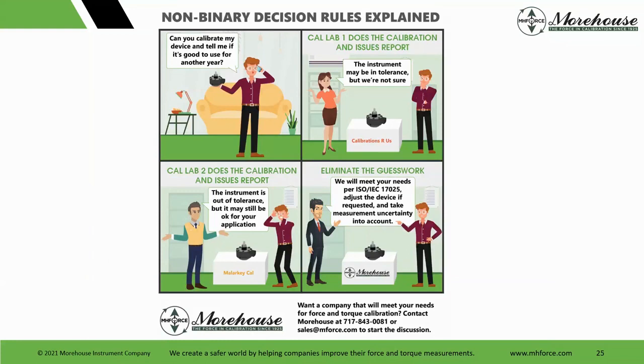So here's what we ran. We came up with this cartoon for it because it's really ridiculous, right? The instrument, so we do the calibration. This is a conditional accept. The instrument may be in tolerance, but we're not sure. Cal Lab 2 issues the report. Conditional fail. The instrument is out of tolerance, but it still may be okay for your application. So that's what you're saying. It's like, is it good? You have all this risk. Is it okay for your application? So we're going to get into TUR, and we made this video, and I think it's worthwhile to show people.